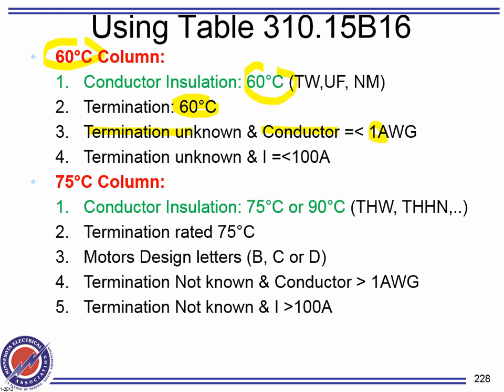If the terminations are unknown and the equipment is rated for 100 amp or less, then you use 60. These are coming from 110.14. These are not from my basement. These rules, I summarized them from section 110.14. And then, all right, one more time. If your installation is 60, don't think about it.